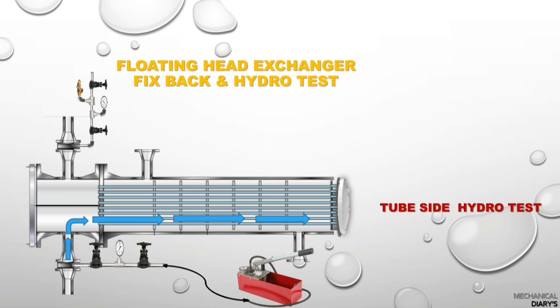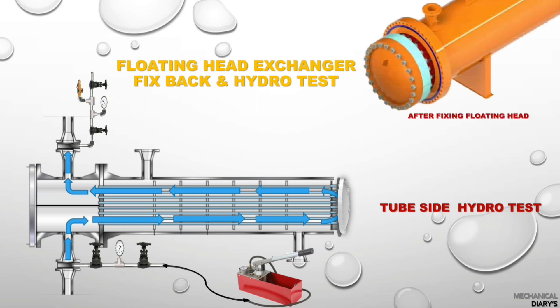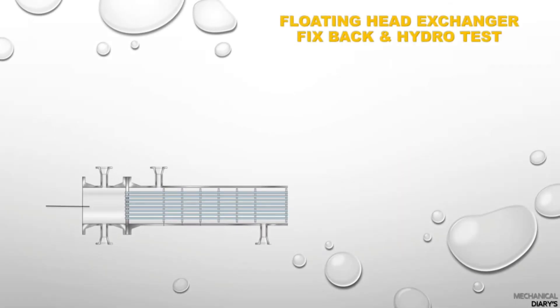Once tightening is completed, pressurize the tube side from the bottom nozzle. Make sure rear venting is completed. Once the pressure is stable, check for leaks at the floating head flanged area and channel head cover area. Before calling inspection, make sure the shell side is completely dry, because any tube puncture will be detected through the shell side nozzle area.